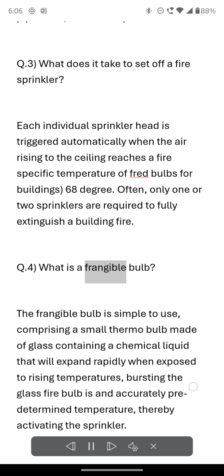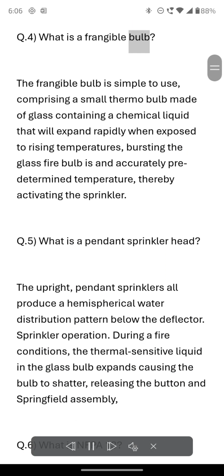Q.4. What is a frangible bulb? The frangible bulb is simple in design, comprising a small thermo bulb made of glass containing a chemical liquid that will expand rapidly when exposed to rising temperatures. The glass bulb bursts at an accurately predetermined temperature, thereby activating the sprinkler.